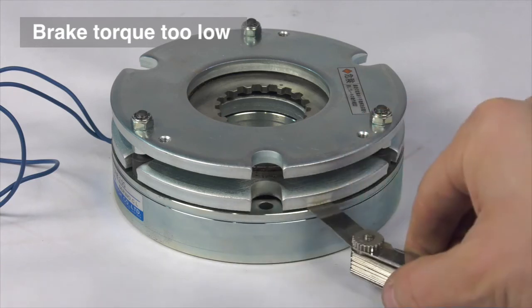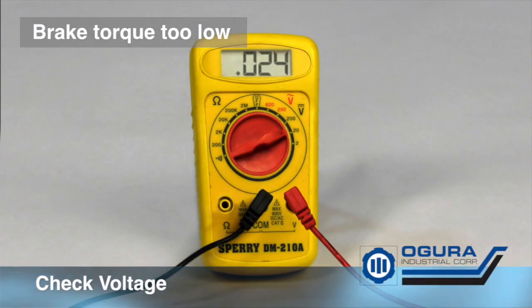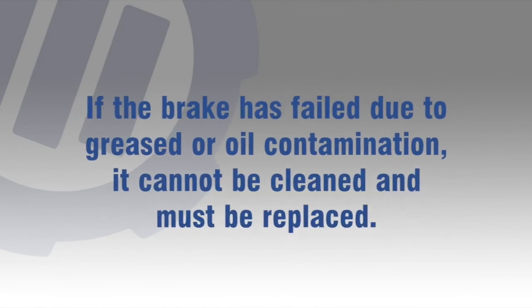Delayed release or brake torque too low. The air gap is too large. Check the air gap. Voltage being applied is not releasing brake. Check voltage. Oil or grease on brake surface. Check for contamination.